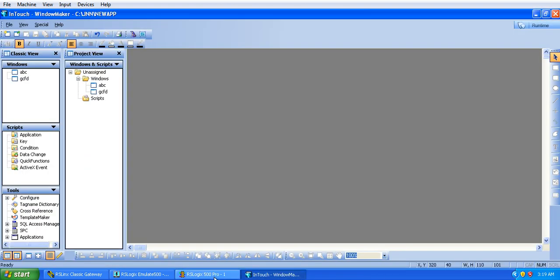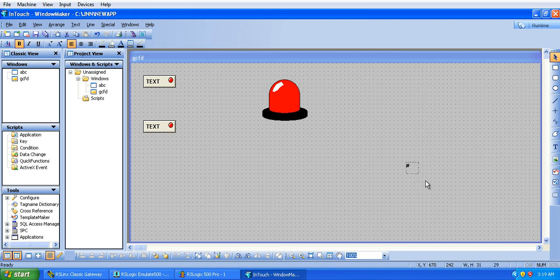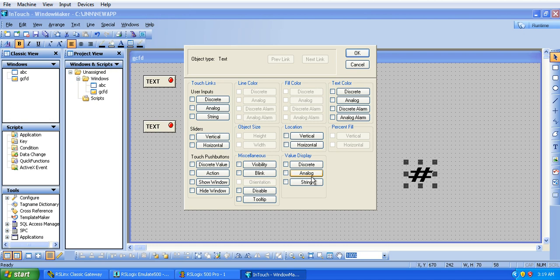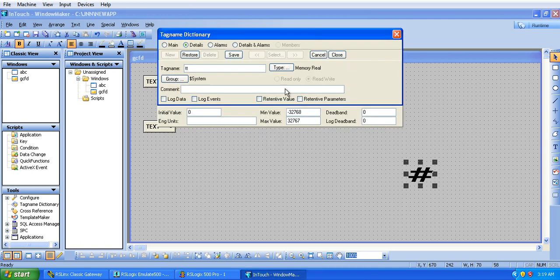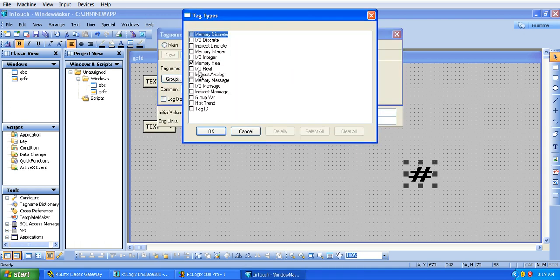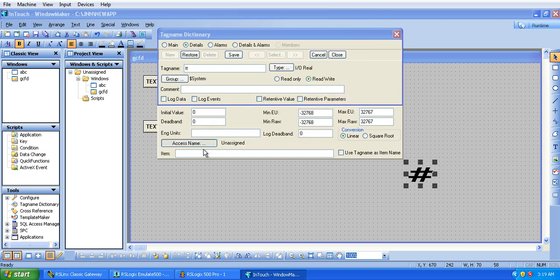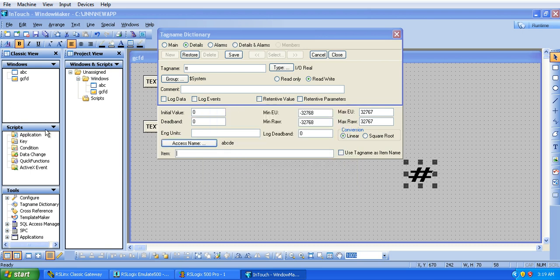For that we will use a hash. In this I will go to value display analog or user input analog. The basic difference is we can change the value at runtime, but here we can only display. So I will use here user input analog. I will give a tag name, analog type memory, input output real of course it is an input output device. Now access name and this item name will be T4:0.ACC, this is the value of the accumulator. T4:0.ACC will show the value of the accumulator at the runtime.